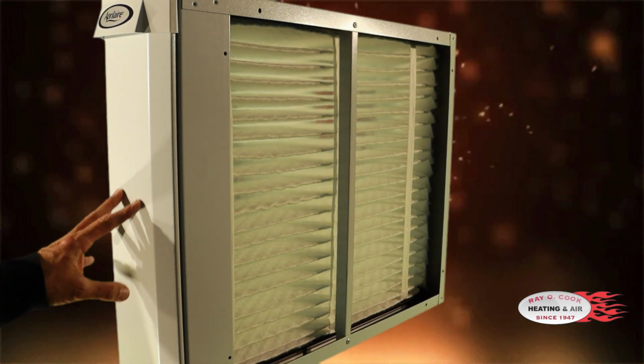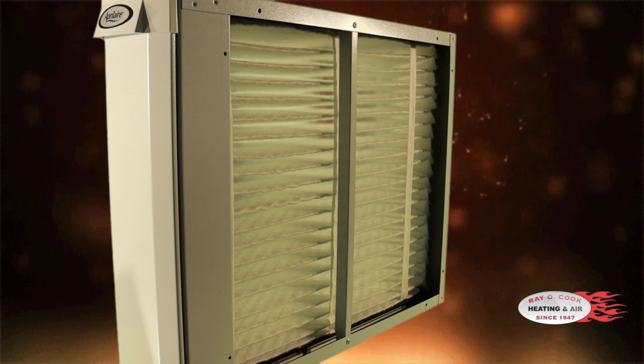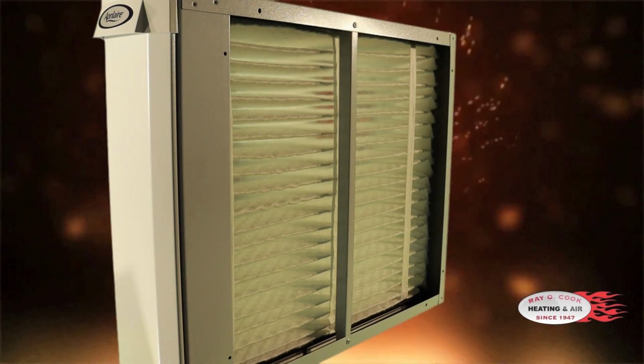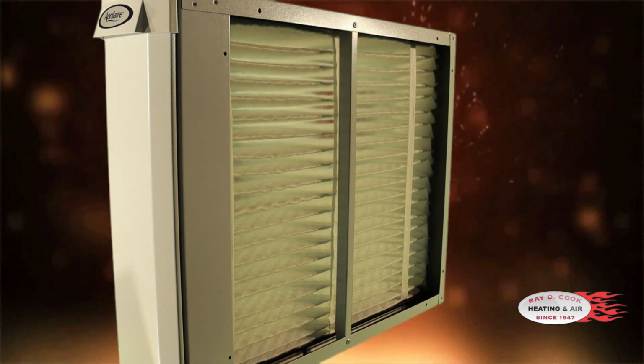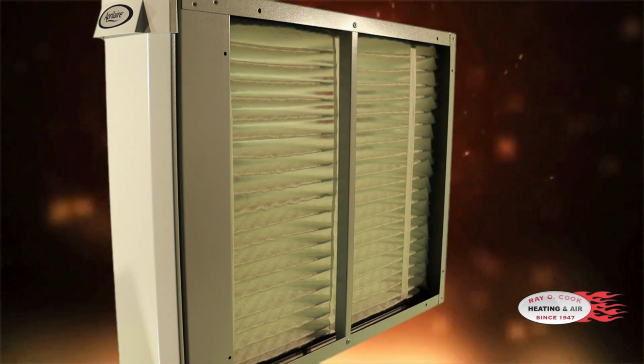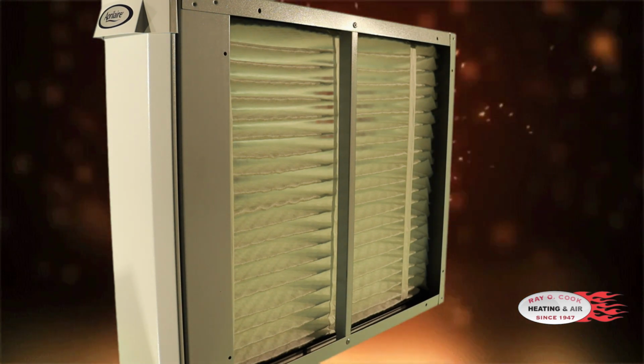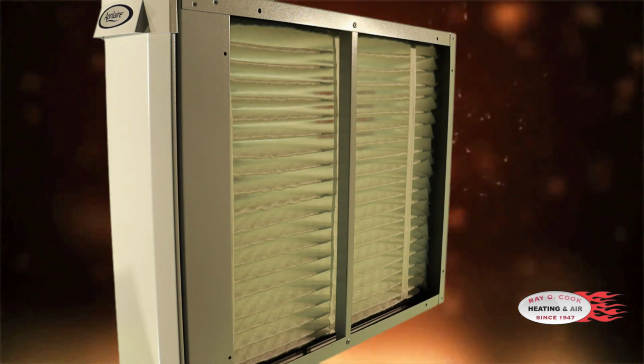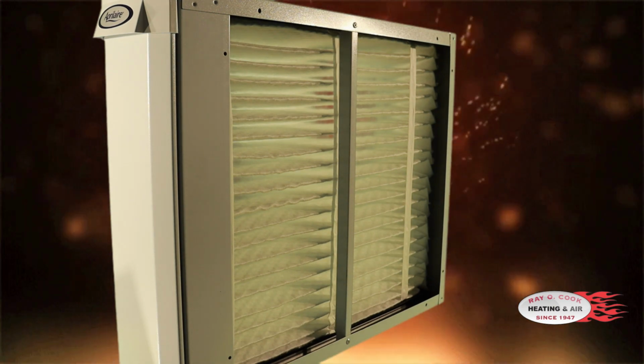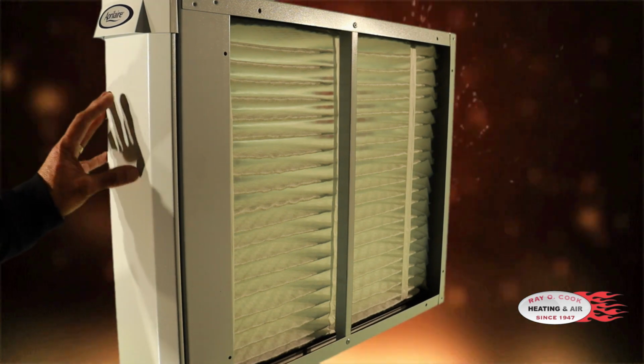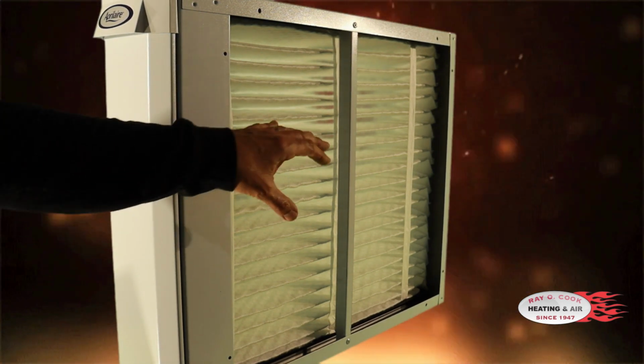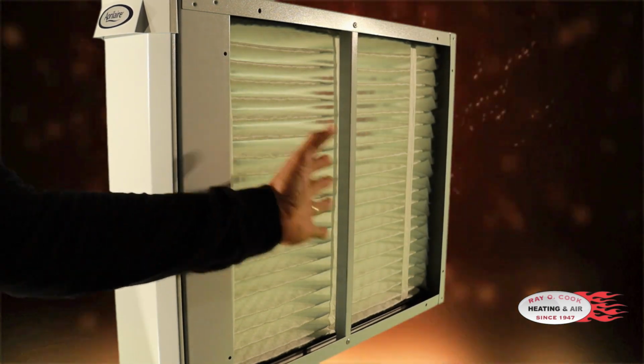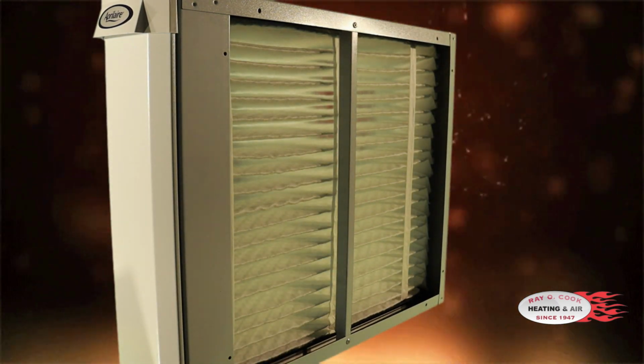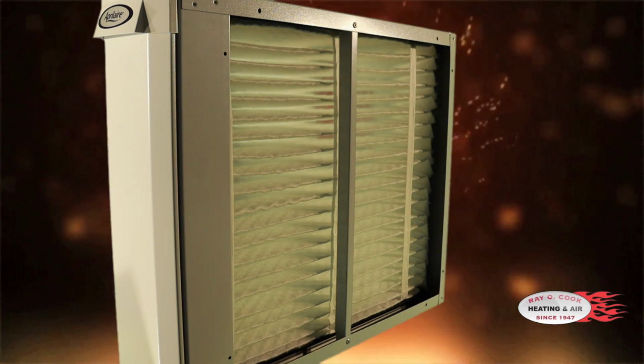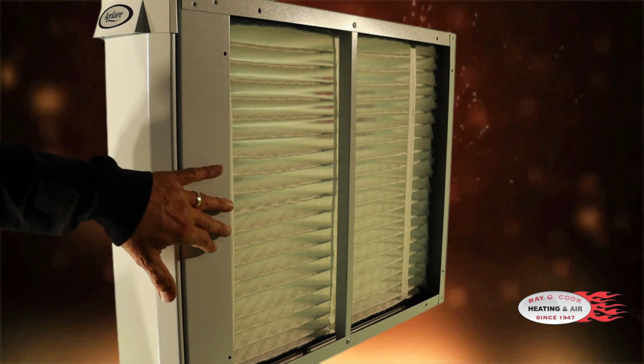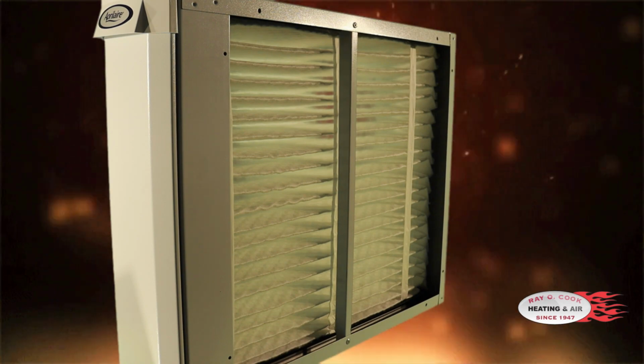This is a cartridge filter. This allows us not to have to cut more holes in the ceiling or deepen the boxes that are there in your ceiling now to try and compensate for high resistance of a filter or low surface area of the filter area. So this gets mounted on the equipment. For instance, if it was on a furnace in the attic, it would be put on the end of the furnace and filter the air right at the furnace. And you would not have any filters in your house. This is the only filter, and it would be up at the furnace.